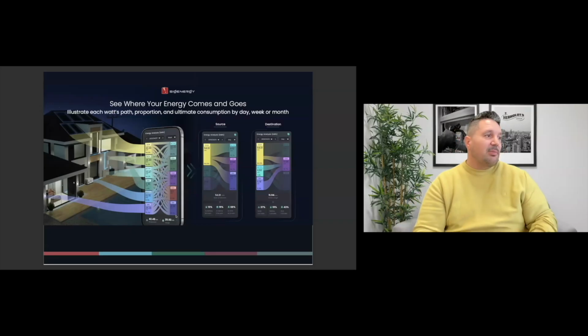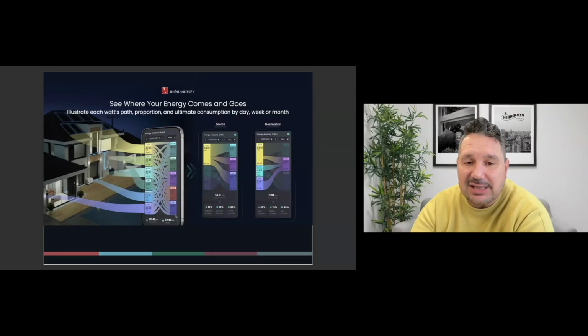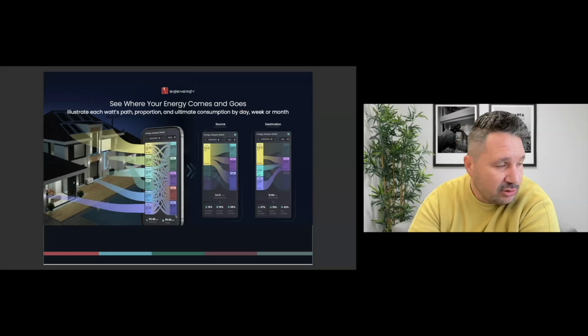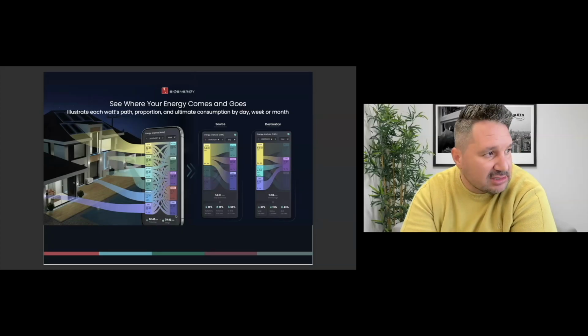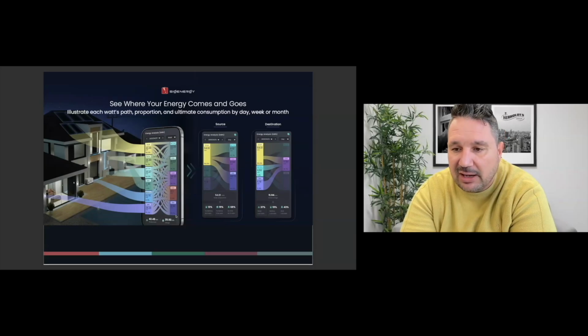It also has a separation of the energy that is inside the battery at that stage. So should you have run a generator for an hour, it'll accumulate what the generator cost is that's put inside the battery. If you charge with the grid for 3 hours, it will then accumulate what those costs were, and then if you charge with PV. So your battery will have, in its full capacity of 100%, stating that 60% was from PV, 20% was from grid, and 20% was from generator.